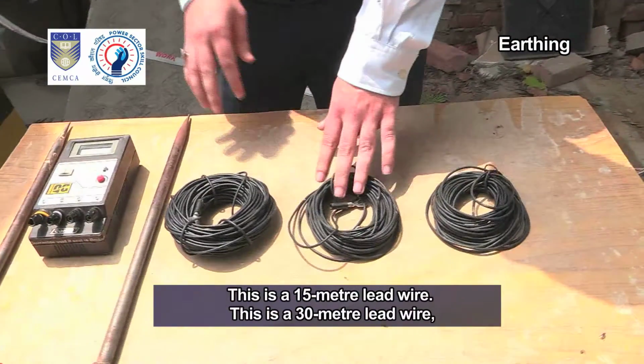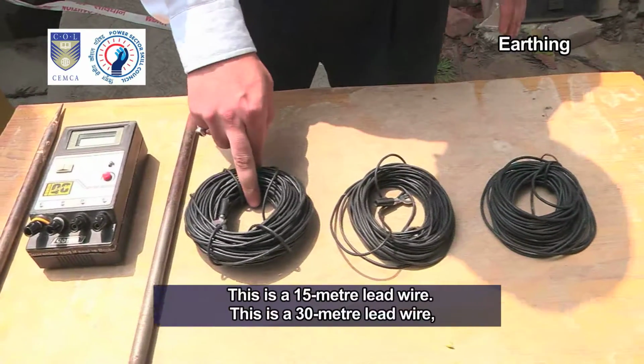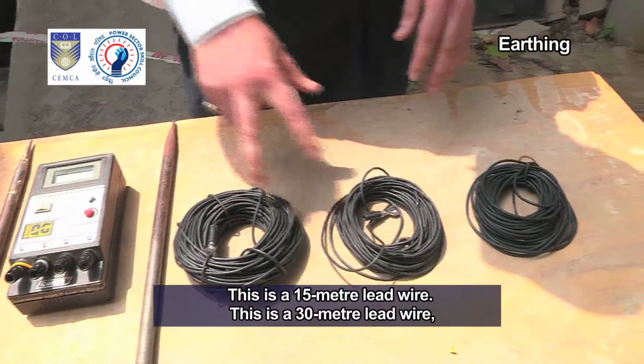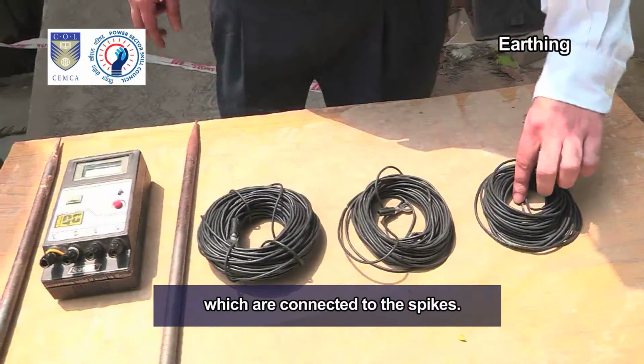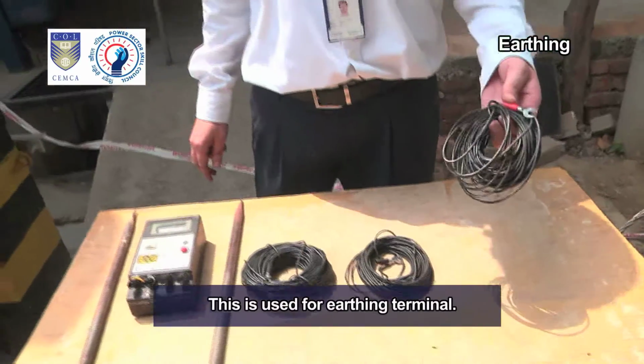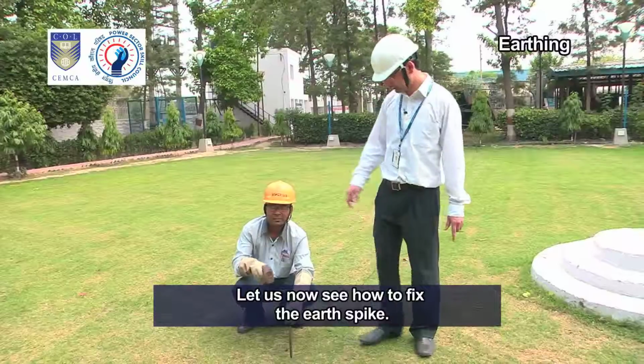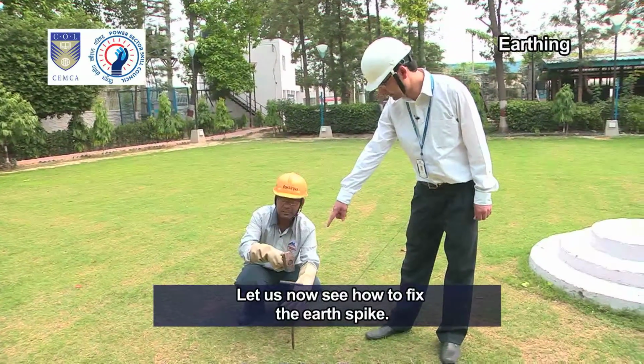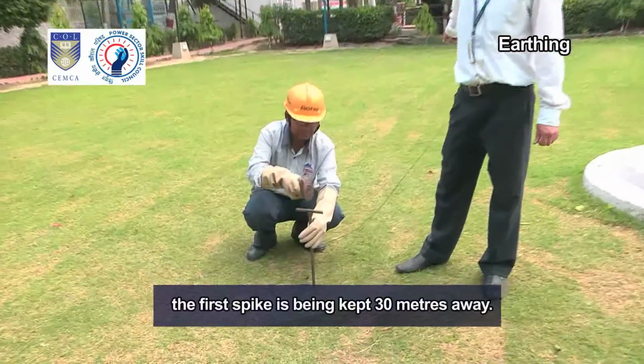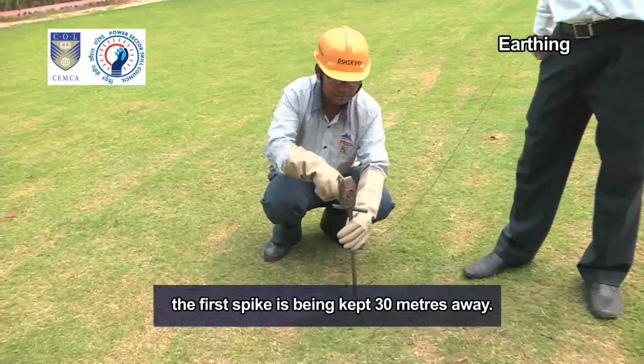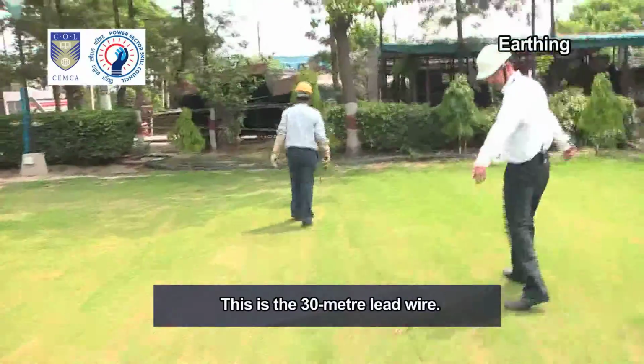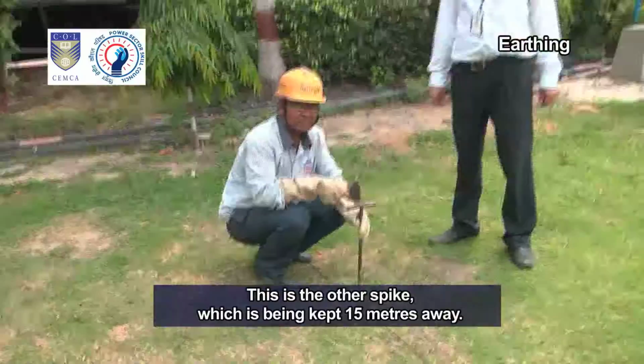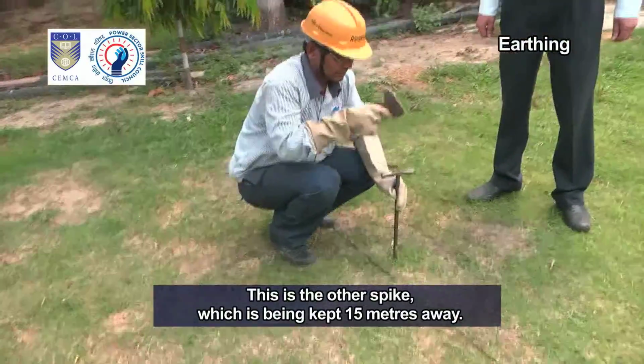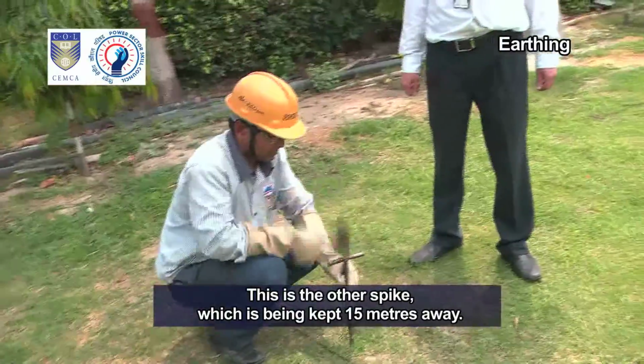This is a 15-meter lead wire. This is a 30-meter lead wire, which are connected to the spikes. This is used for earthing terminal. Let us now see how to fix the earth spike. Here, the first spike is being kept 30 meters away. This is the 15-meter lead wire. This is the other spike, which is being kept 15 meters away.